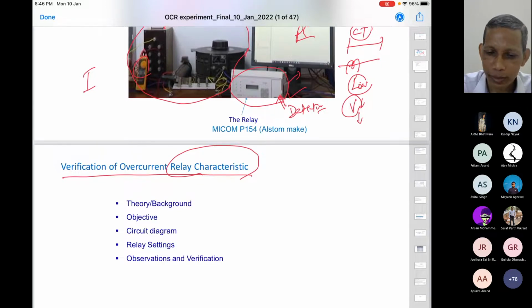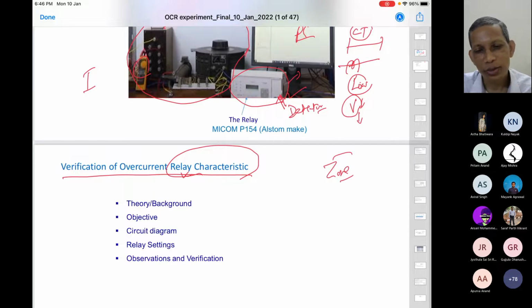This is required from the selectivity point of view. Another term, coordination, will also come up, and we'll see what the different requirements are from a system protection perspective, so that the relay acts accordingly. I told you that it is not that wherever it finds the current to be high, the relay should trip. It has to be in a selective way. It should isolate only if it identifies that the fault is within its jurisdiction, its assigned section, which we call a zone. Agree? Each relay is assigned a zone or area, so it should look after that. If the fault happens beyond that zone or assigned area, line or segment, it should remain silent.